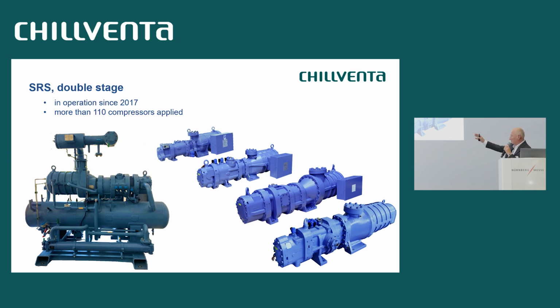Again, very compact solutions. The only downside of double-stage compressors compared to a booster system is that you cannot apply a side load on the high temperature side. So it is the right solution for dedicated compressor systems to one blast freezer, one spiral freezer, for example, or one low temperature cool room without a side load.